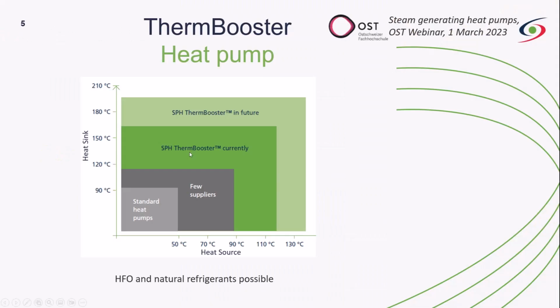So now to the heat pump. We call it ThermBooster. The area in which we feel comfortable is, let's say, on the heat sink side above 90 degrees, up to currently 160, 165, depending on whether we are using steam or hot water. So this topic here is steam: 160 degrees when we produce direct steam. On the heat source side, we could go lower, but usually we get temperatures from 50 degrees or above. In future, we could also go higher.